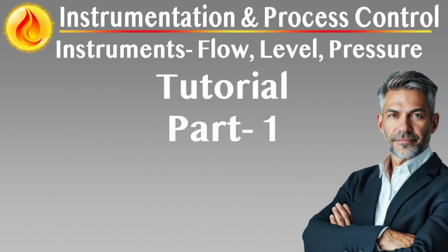Explosion safety through classification-driven hardware selection. Instrumentation in hazardous zones must meet zone-specific protection standards. Ex ia is mandatory in Zone 0, while Ex d, Ex e, or other IEC-recognized types may be suitable in Zones 1 and 2 depending on national overrides. Full certification, e.g. CENELEC, IECEx, must accompany all devices, and field personnel must validate compatibility with site-specific area classifications.